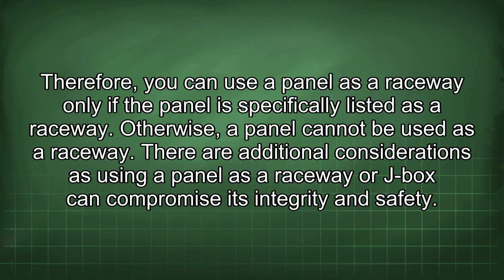Therefore, you can use a panel as a raceway only if the panel is specifically listed as a raceway. Otherwise, a panel cannot be used as a raceway.